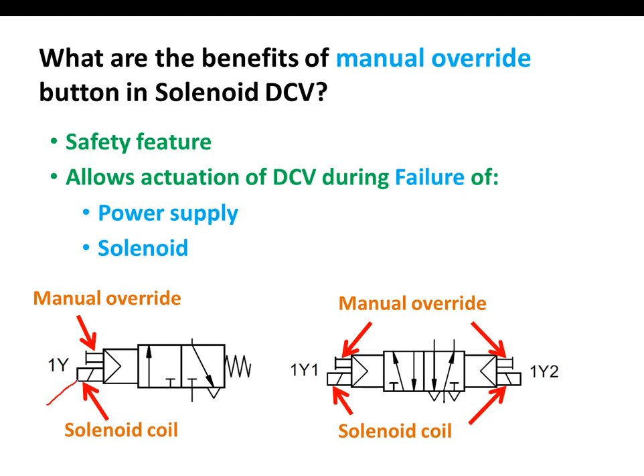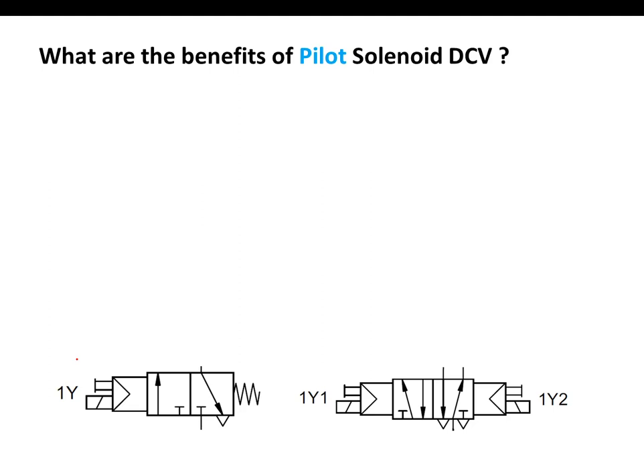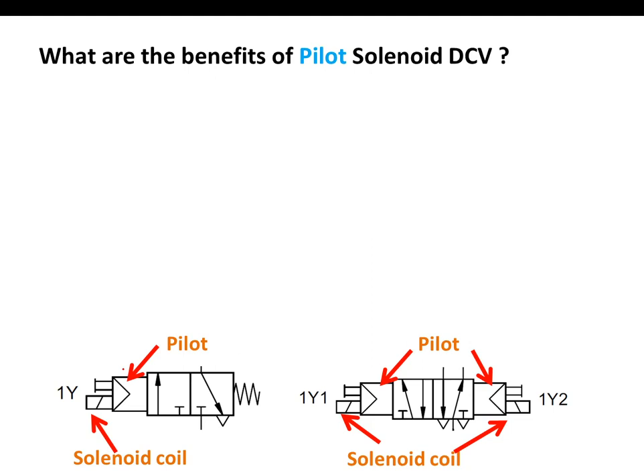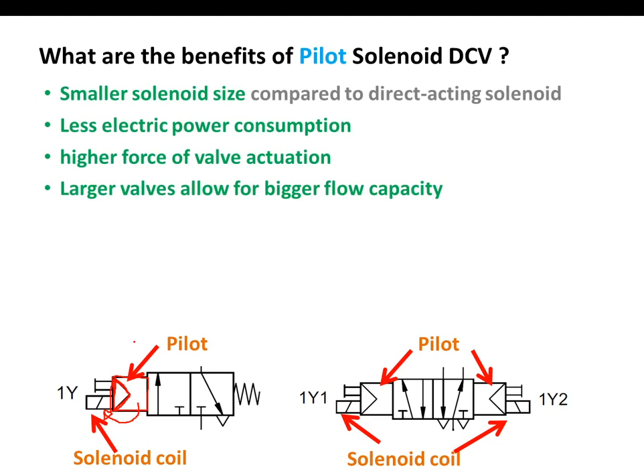What are the benefits of a pilot solenoid DCV? A pilot is an assistance accessory which uses pneumatic pressure — shown by a triangular shape — to assist our solenoid. By the aid of this pilot, we can reduce the size of our solenoid, have less power consumption since the solenoid is smaller, and increase the force of actuation.